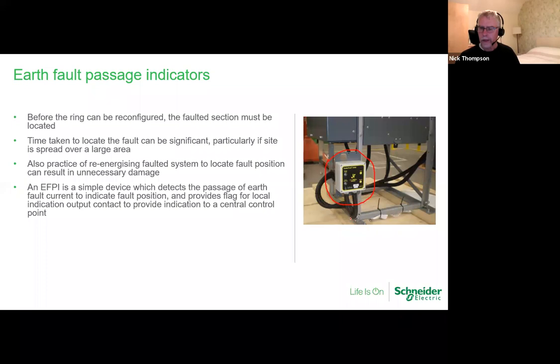And we do have a CT which is located inside the cable box. That CT goes around all 3 cores, and it's commonly known as a core balance CT with the appropriate earthing strap to allow the correct earth flow current. So the box will actually work out.